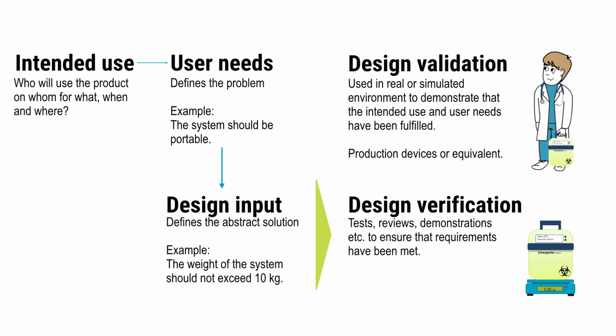Looking at our example from before with the portable product, we might let a few users carry the device and thereby conclude that yes, the device is in fact portable. It is of course not always that easy to do design validation. Sometimes you cannot show that intended use and user needs have been met with anything less than a clinical investigation and use on real human subjects.